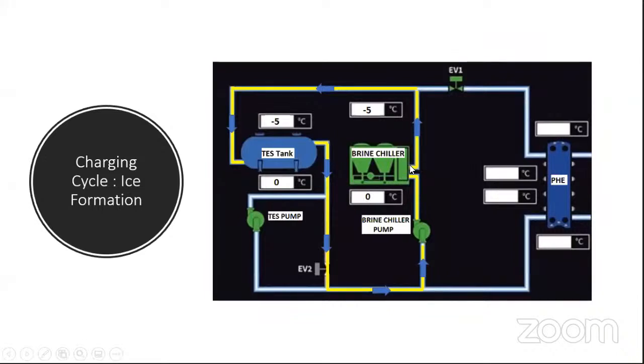So how is it happening? Let us start from here. That minus 5 degrees centigrade brine solution is being pumped into the thermal storage tank to form ice inside the tank. And after gaining heat from the water and forming some ice, the warmer 0 degree centigrade brine solution comes out and goes back to the chiller with the help of this pump operating. So this is the charging cycle. See, that's a dual mode chiller. In this case, the PHE is not in operation. It is isolated with the help of a valve.